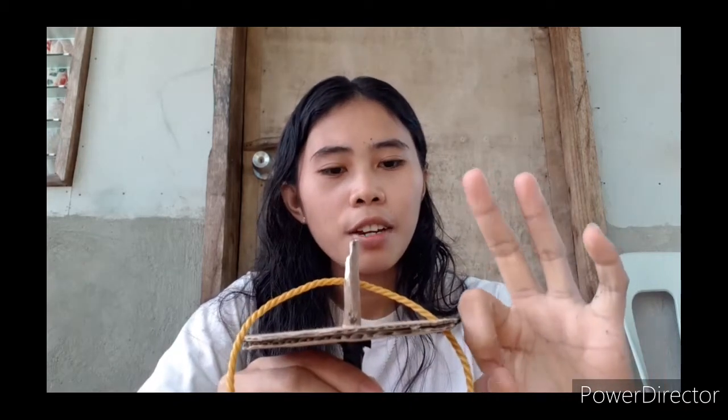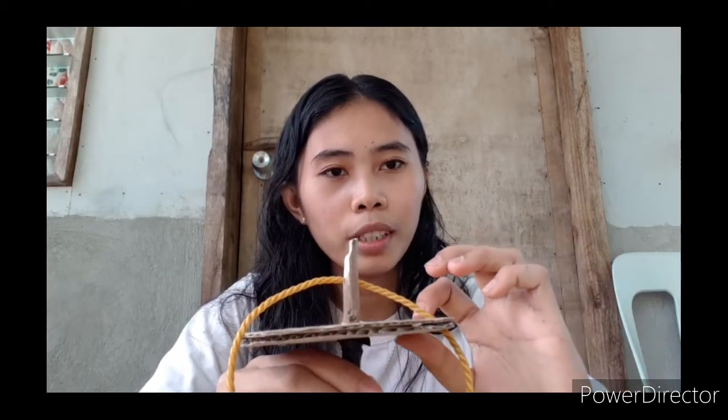For example, I will enter at 1, and then for the next turn of the coil, I will enter at either number 2, 3, or 4. For this progressive wave winding, I have a coil pitch of 3. So if I enter at 1, for the next turn I will add 3 to 1 so that I will know where to enter next.